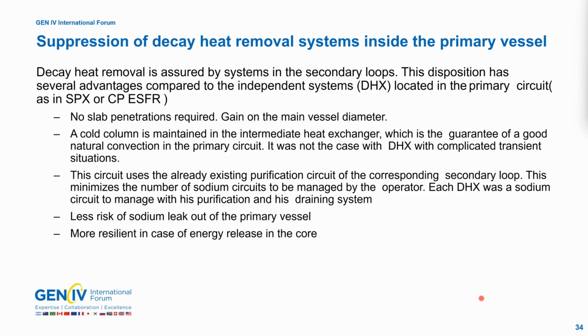In thermohydraulics, we have a cold column that is maintained in the intermediate heat exchanger, which is a guarantee of a good natural convection in the primary circuit. It was not the case with DHX, because with DHX, you have very complicated transient situations before you cool the core of the reactor. The circuit uses the already existing purification circuit of the corresponding secondary loop. So we minimize the number of sodium circuits. We have no new sodium circuit to manage by the operator. The DHX of Superphénix was a sodium circuit to manage with purification system and draining system, and all that had a complexity for the operator.